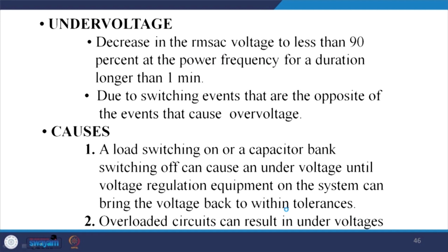Similarly, you can have under voltage, which decreases the RMS AC voltage to less than 90% at the power frequency for a duration of more than 1 minute, due to switching events that are the opposite of the events that cause over voltage. Causes: a load switching on, or a capacitor bank switching off, can cause an under voltage until voltage regulation equipment on the system brings the voltage back within the tolerance level. Overloaded circuits can also result in under voltages.